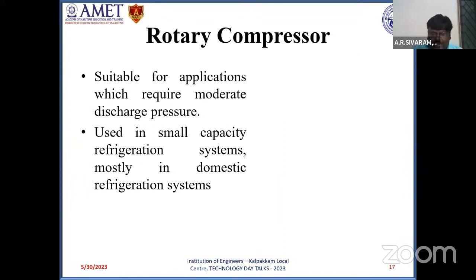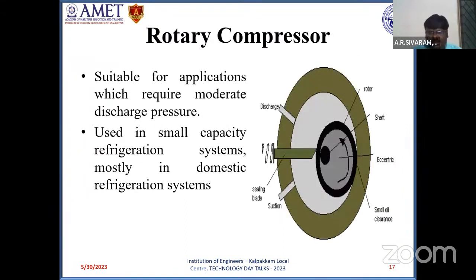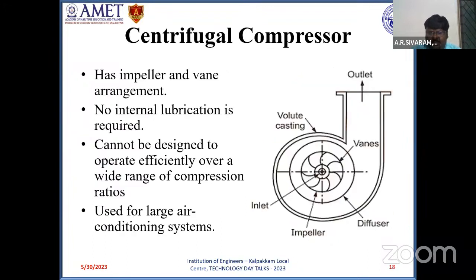Rotary compressor: this has a rotor present in it. Rotary type compressors are preferred for refrigeration systems with low refrigeration capacity. Rotary compressors of the hermetic, or closed, type are preferred for domestic refrigerators and domestic air conditioners. These types of compressors are preferred where there is a requirement of moderate or low discharge pressure, so power consumption is very low in a rotary compressor.